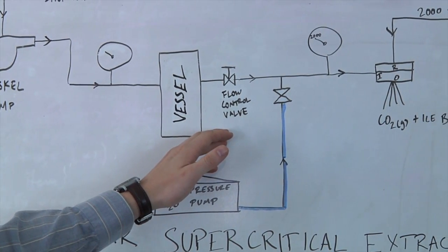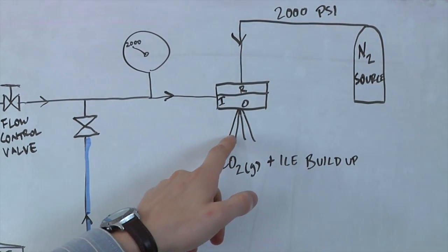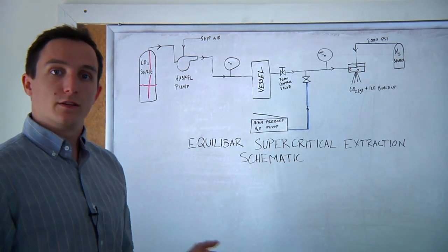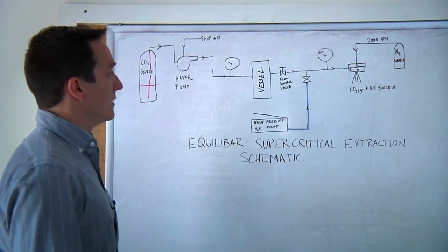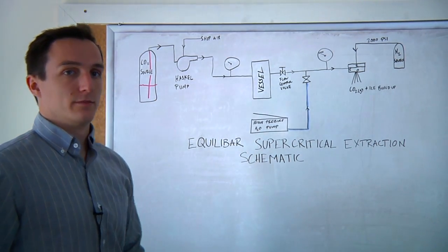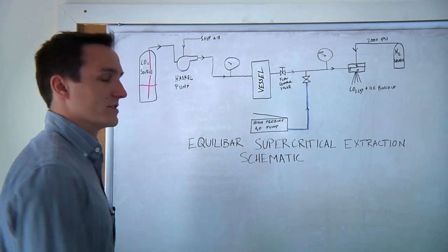From there, we have a flow controlling valve, and in this particular setup, the Haskell pump and the Equilibar both generate pressure. In this case, the Haskell generates pressure on the inlet, and the Equilibar is on the outlet. So you need some DP device to have constant flow throughout the system. So that's what our flow controlling valve does. But again, in your particular setup, it could be different.